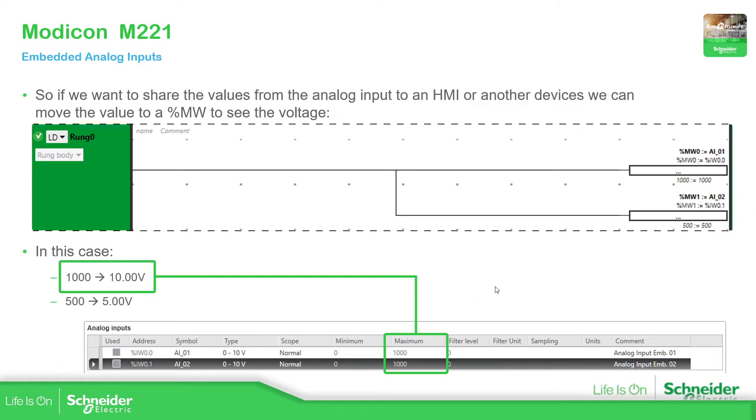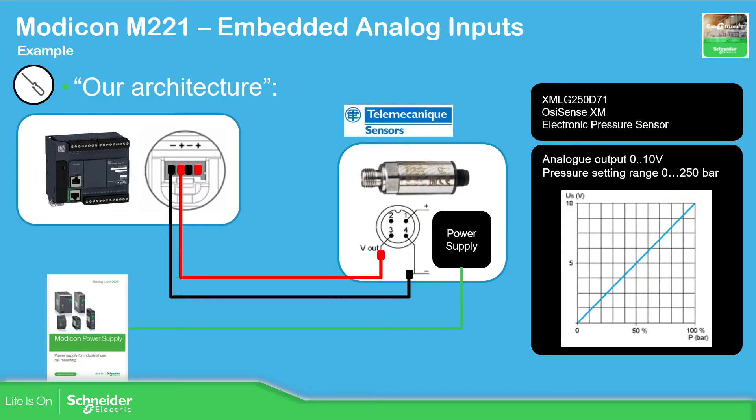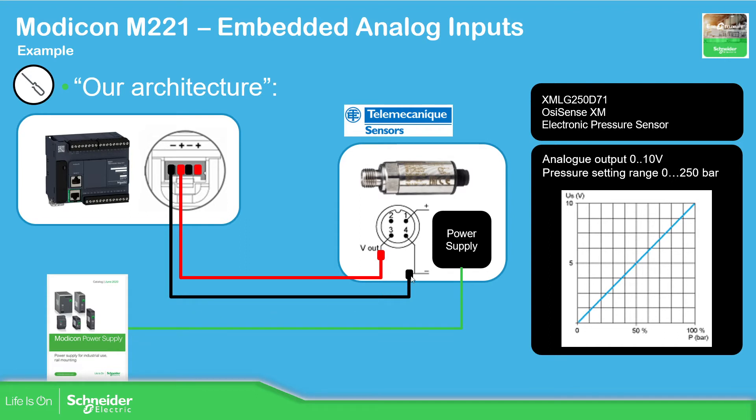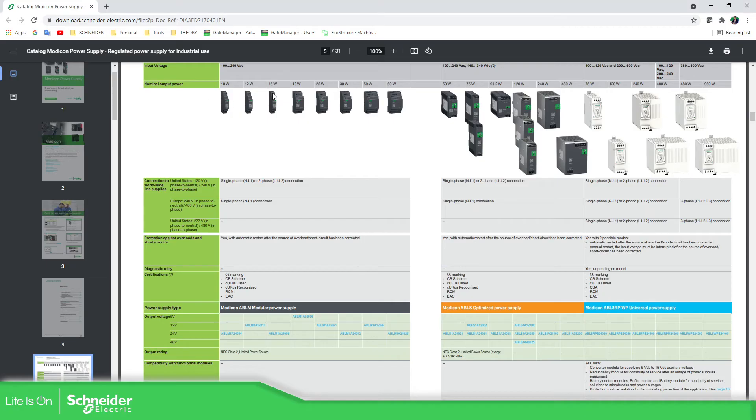In order to test this, because I don't have the sensor, we're going to see what is the idea. I have selected this pressure sensor that goes from 0 to 250 bars. The output of this sensor goes from 0 to 10 volts, so it's compatible with the analog input that we have on the controller. And if we want to communicate this, this should be the connection. I'll put here the common, and if we require a power supply, we have the Modicon power supply.